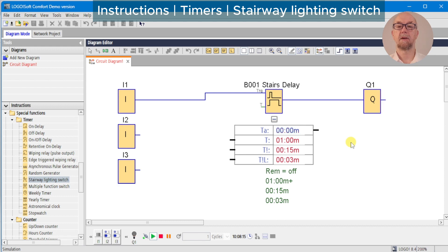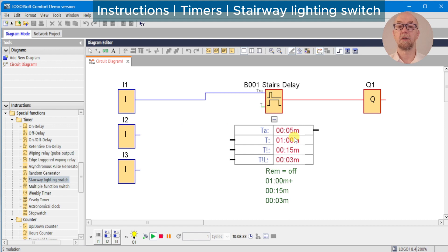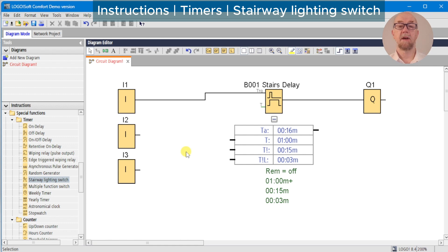Note also this is edge-triggered, so if the first user switches on the lights we can see the timer is running. If a second user comes along and switches the lights, the timer resets and they have the full time period to negotiate the stairs. For multiple landings on the stairwell we may have a button on each floor.